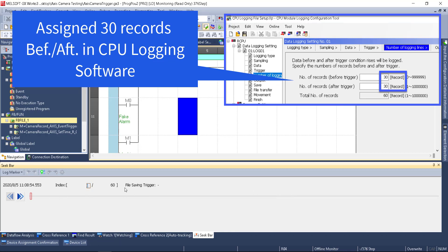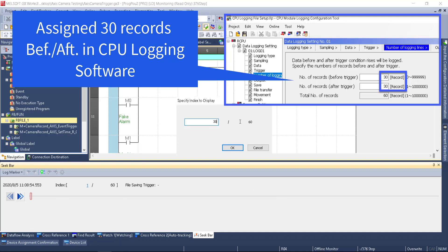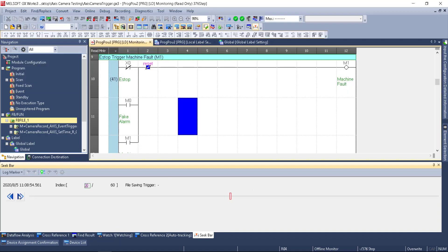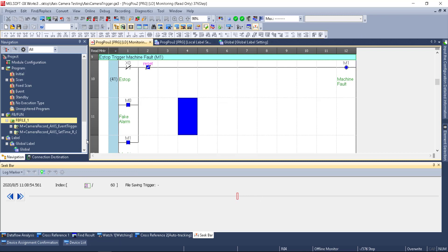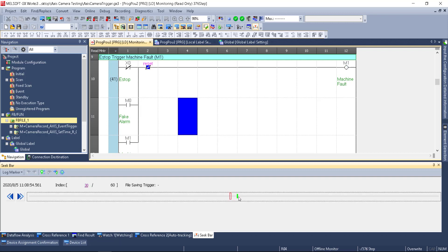We're basically in an online-looking state but it's actually offline monitoring — this isn't monitoring the PLC, it's monitoring the logged file. I've got 30 records before the event and 30 after. At record 30, M1 is still off; at record 31, M1 is on — that was my trigger. I can click back and forth on the seek bar to see what drove M1, and it was the fake alarm M0 from the HMI. I can go exactly to record 31 and add a log marker — that's always there, a permanent reference point.